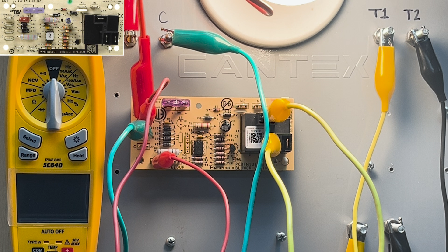This board allows me to plug them onto the M2 and M1 spots on the board, where it's safe and I know where they are. If I need to change speeds, maybe from medium to high, I can do that. Right now they're normally closed, coming up to my T1 to energize my light. That would represent the medium speed tap that I would typically use. So we have this speed up terminal down here - I want to show you what that's for in just a second.